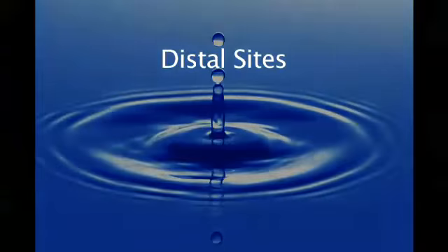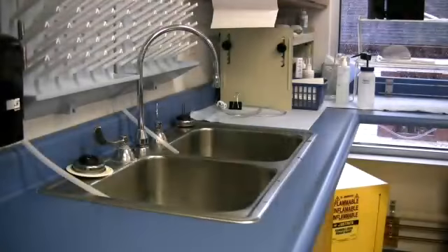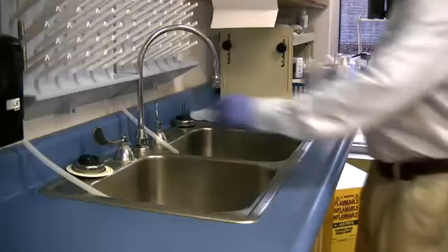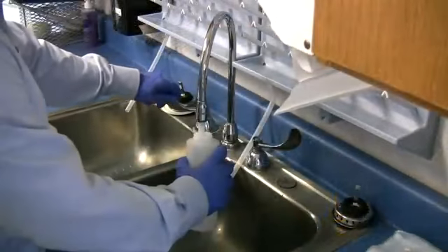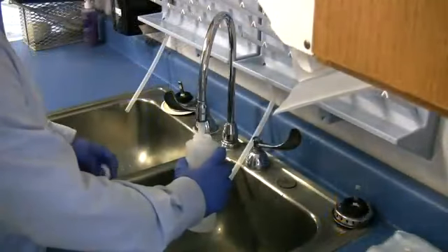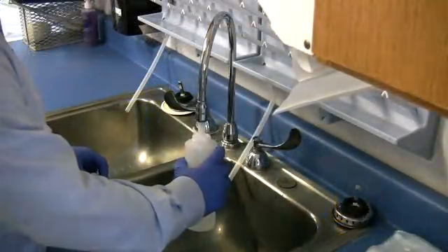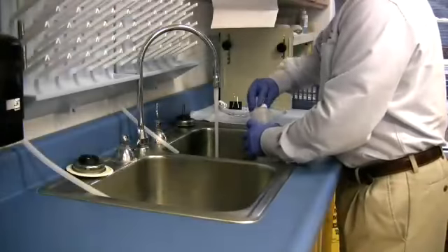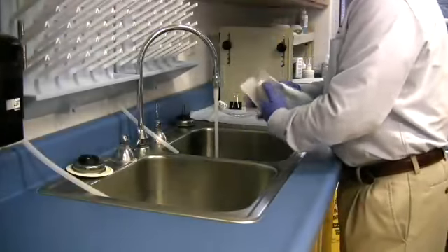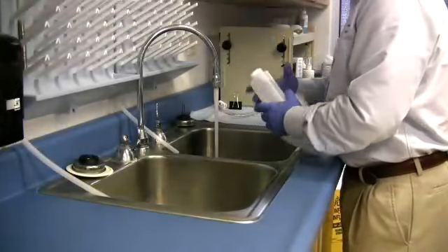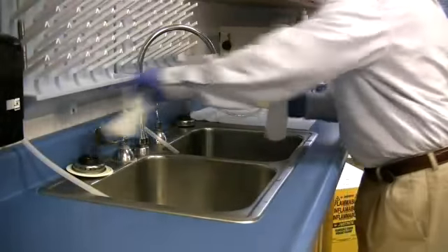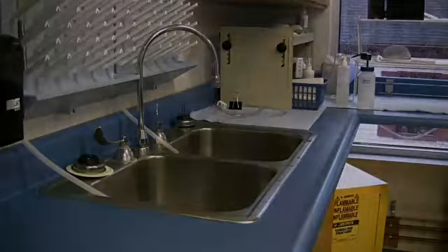Next, we'll look at sample collection from a distal site or sink. Sample collection for distal sites of potable water systems varies slightly from the collection of potable hot water tank samples. Collect samples from locations both close to and far away from the hot water tank. Showers and sinks are the most common areas to test. The sample should be collected immediately, as Legionella tend to colonize the sink or shower head. Fill to within 1 inch from the top and do not fill the bottle completely.